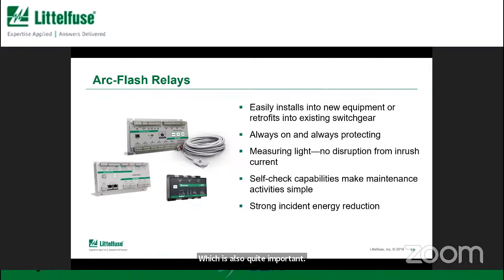Another item is that these protection relays, I'll talk about the specifics in a moment, but they are designed with some very interesting self-check functions. Because it's a safety relay, we really want to make sure that it's doing its job, and because we're relying on it, we're trusting it to be there when there is an arc. So there are several layers of self-check to make sure the system is operating as you expect. And of course, they are one of the ways that you can achieve a very strong reduction in the arc flash energy.